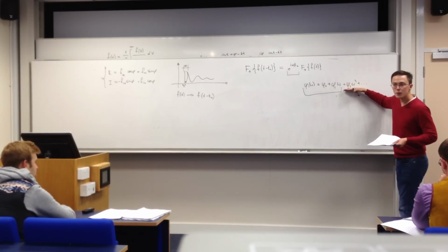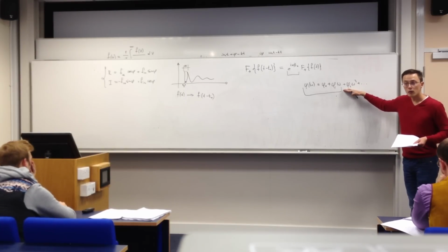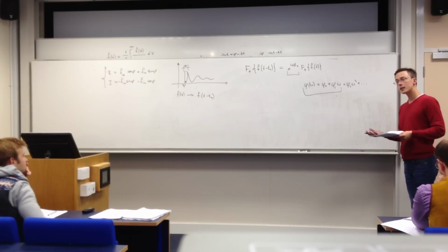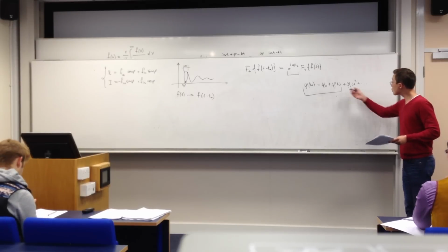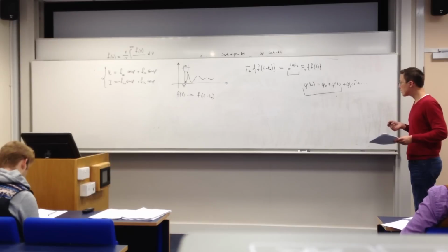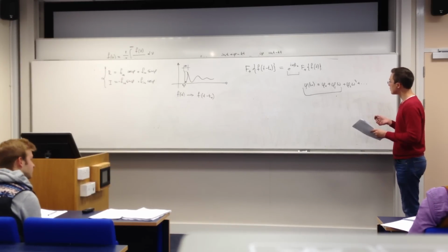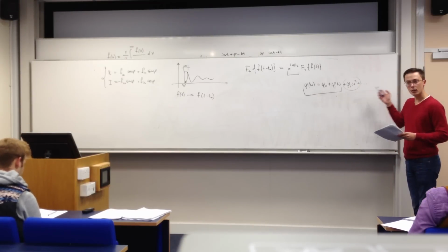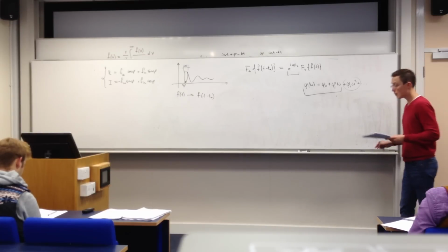Beware, if you have to correct phases to quadratic order or higher, something is wrong. Normally, a spectrum that comes out of a valid procedure without hidden distortions or causes of those distortions should not need the quadratic terms in the phase corrected. If it does, then you're probably using shaped pulses and you're probably not doing a good job of using them. So that's something to watch out for. Make sure that if you have extra correction terms in your phase, highly nonlinear ones, you understand where they're coming from.